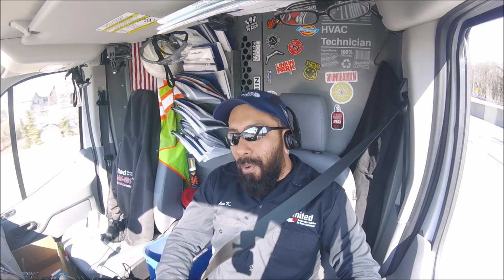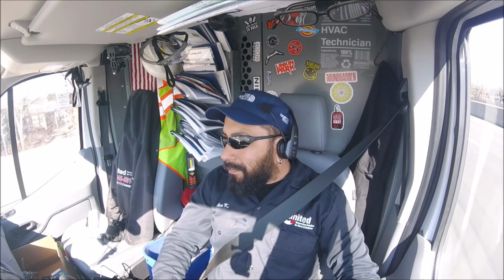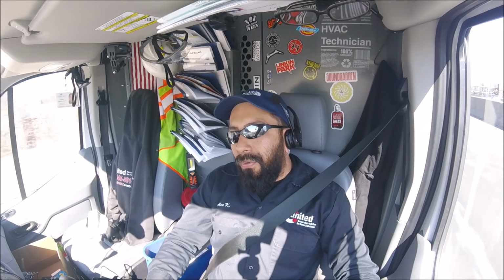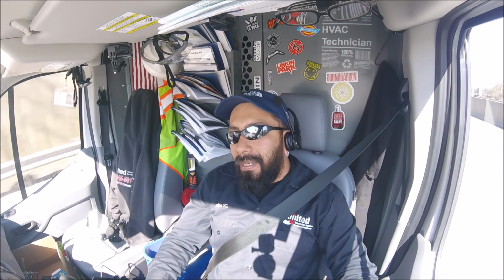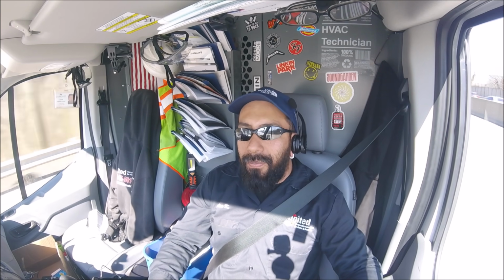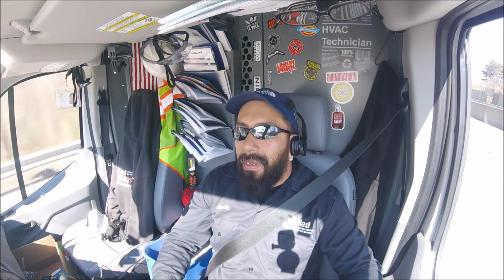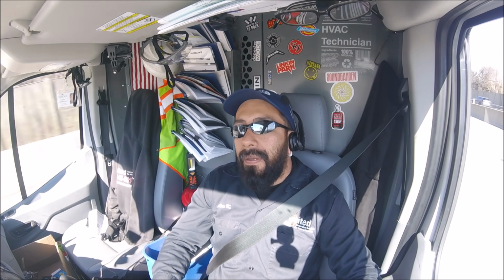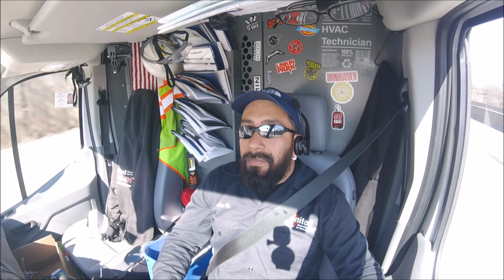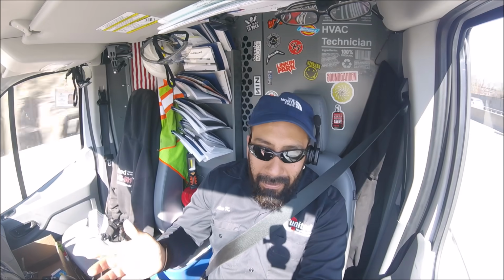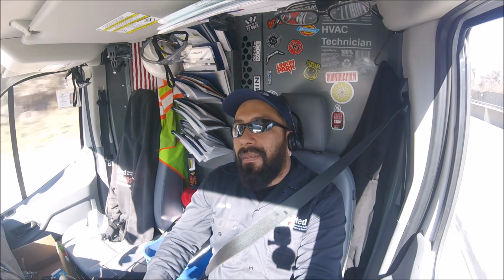At that point the guy was all nice with me. I'm coming down the roof, and I try to make this as painless as possible. So what I do is just the paperwork. I call the management company and talk to them and say, look, this customer has a cracked heat exchanger. I have to shut the gas off for safety, and they've got no heat, and this is their only source of heat. So you may want to contact these people and tell them to get some heaters. I don't know how it's gonna work, but this is what's happening.